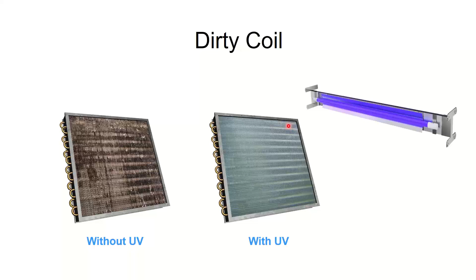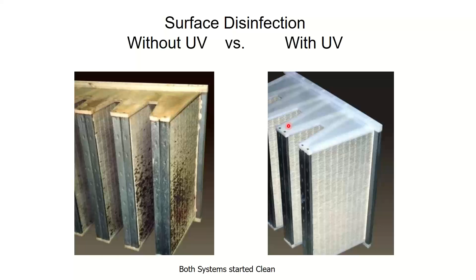Well, the two problems with that are: one, the stuff flaking off is going to clog up my drain pan, that's not good. And two, if I just sold the customer a clean coil and it still looks like that, they're going to be grossed out. So I need to manually clean the coil and then use the UV bulb to keep it clean. It's more of a maintenance type thing. That is the absolute best use for the UV bulbs—cleaning coils and keeping coils clean.